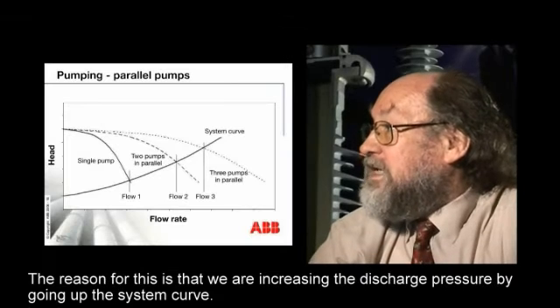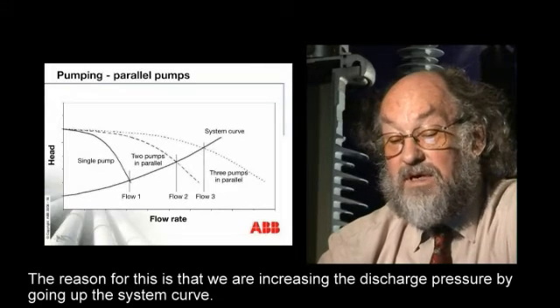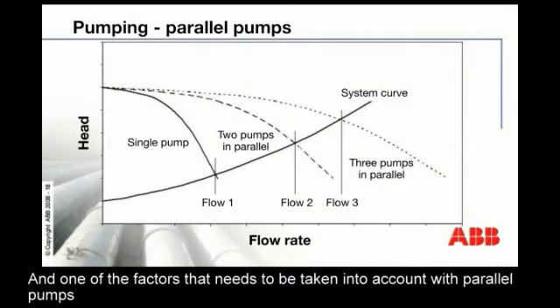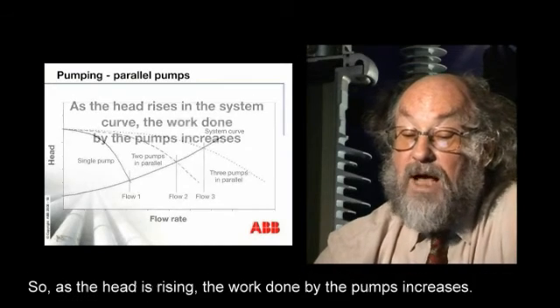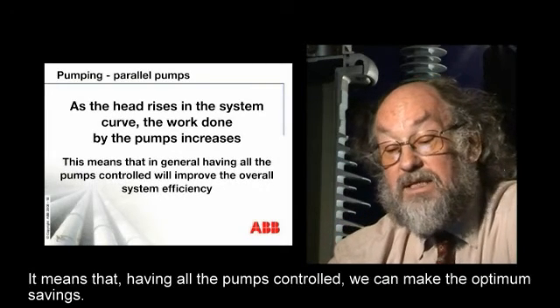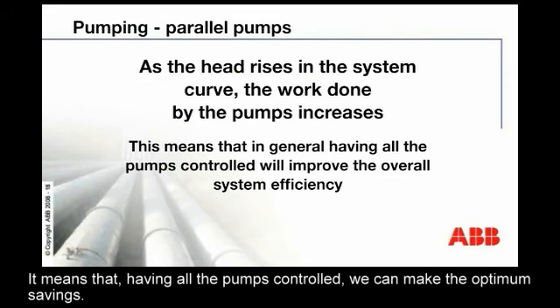The reason for this is that we're increasing the discharge pressure — they're going up the system curve. One of the factors that needs to be taken into account with parallel pumps is that the greatest energy savings can in fact be achieved by running all three pumps on variable speed. As the head is rising, the work done by the pumps increases, meaning that having all the pumps controlled gives us optimum savings opportunities.